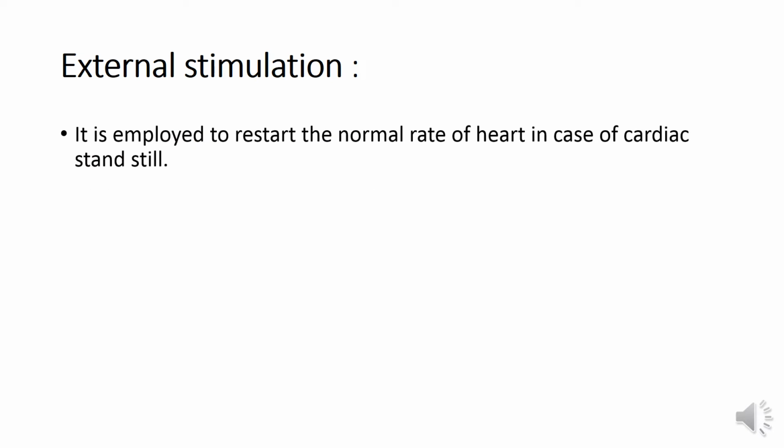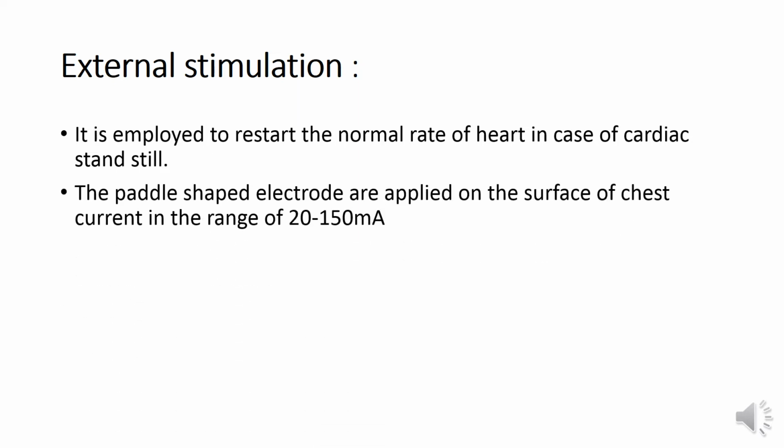Next is the external stimulation. In this method, to restore the normal rate of the heart in the case of cardiac standstill, we have to use a paddle shaped electrode. This will be applied on the surface of chest. The current range is 20 to 150 milliampere.